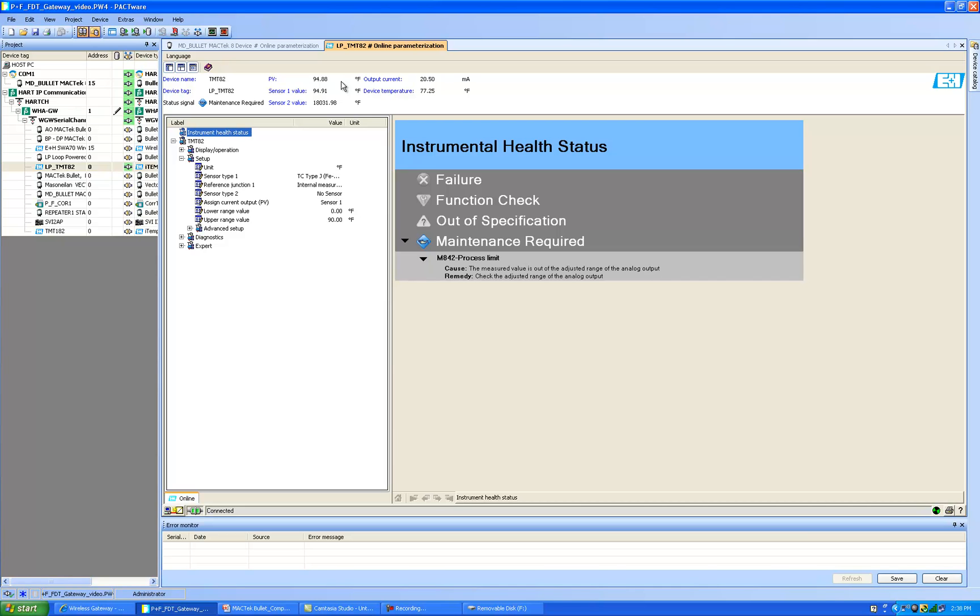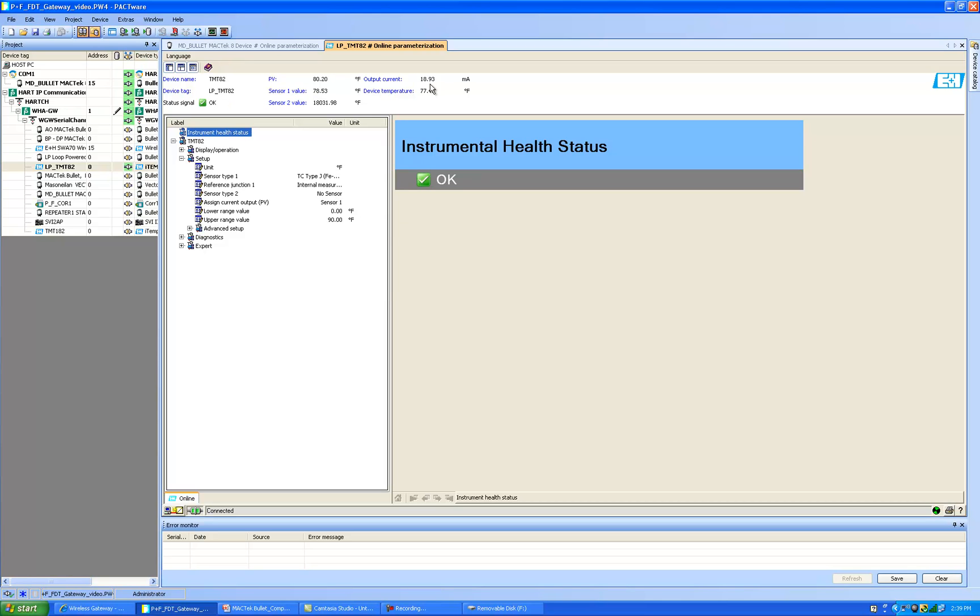As I let go of the thermocouple this will come back in range, our current will drop and the instrument will go back to normal operation. So here it is the thermocouple is cooling down, we're back in the range below 90 degrees and the instrument health is okay.